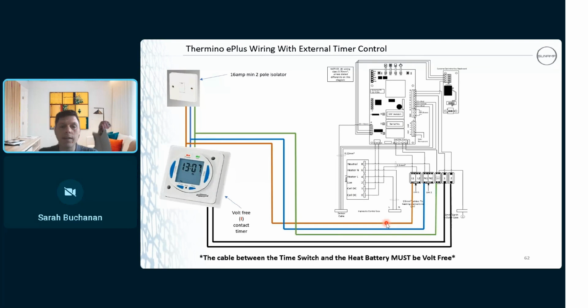If you're fitting a timer, it has to be a volt-free contact timer. You wire the volt-free contacts into 1 and 2. So you remove the charge link, run your 2-core from there to your volt-free contact timer, and then it comes on and goes off as and when there's a demand. Even if there's a demand from the heat battery, but the timer's off, the element's not going to come on. So that's almost like your master control, but it must be volt-free.